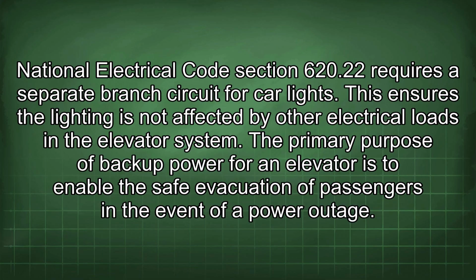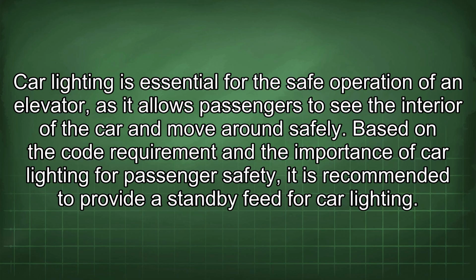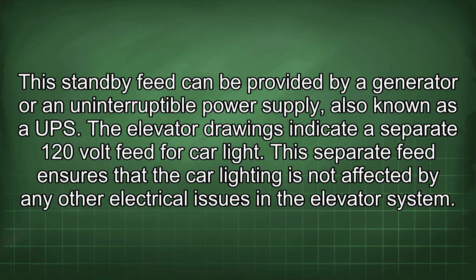The primary purpose of backup power for an elevator is to enable the safe evacuation of passengers in the event of a power outage. Car lighting is essential for the safe operation of an elevator, as it allows passengers to see the interior of the car and move around safely. Based on the code requirement and the importance of car lighting for passenger safety, it is recommended to provide a standby feed for car lighting. This standby feed can be provided by a generator or an uninterruptible power supply, also known as a UPS.